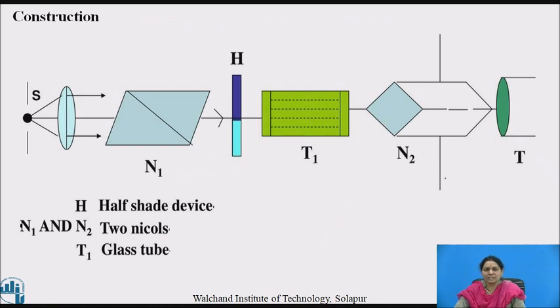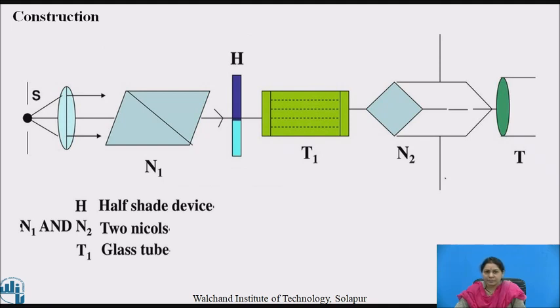Let us see the construction of the polarimeter in detail. A polarimeter consists of a glass tube for holding the solution under test, held between crossed nicol prisms. Beyond the polarizing nicol prism, a half-shade plate is located, used for accurately adjusting the two nicol prisms to the crossed position. Light from a monochromatic source is made parallel by lens L and then incident on polarizer N1. The light from the polarizer is plane polarized, then passed through a half-shade plate and through glass tube G containing the solution. The light emerging from the solution is incident on analyzer N2, observed through telescope T, and the rotation of N2 can be measured with the help of a scale.